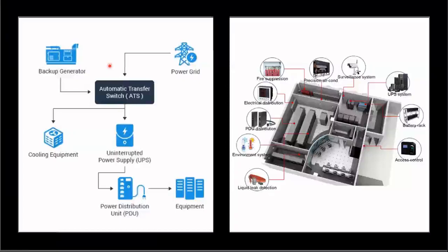Okay, so power comes from the utility, and this is the automatic transfer switch. From here, the data center starts. The automatic switch will transfer the power: if the utility power goes off, it will transfer to the backup generator. Otherwise, power will flow through the utility. It will go through the UPS. The UPS will clean the power, and it will also protect the equipment whenever there is a power failure. Other power will also go to the cooling equipment, because cooling is required in a data center. Why? We will see in the further slides.